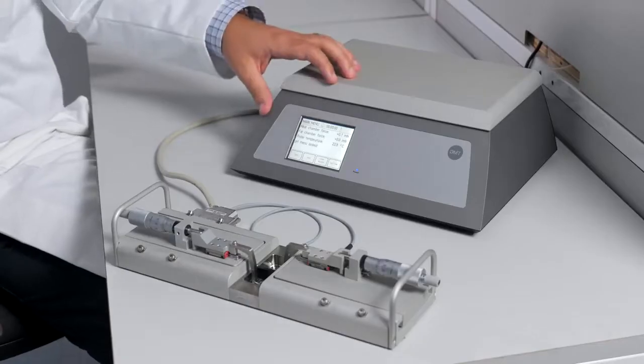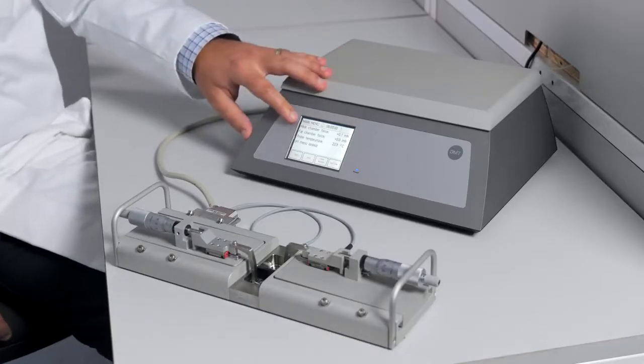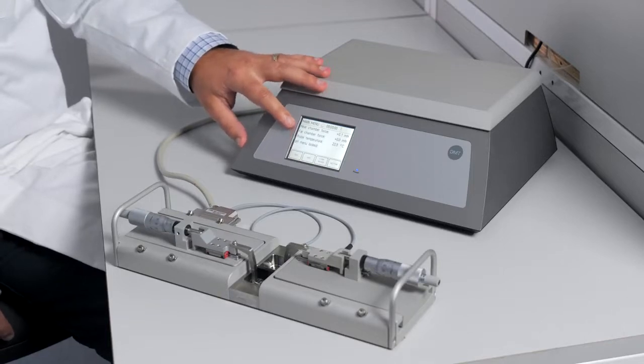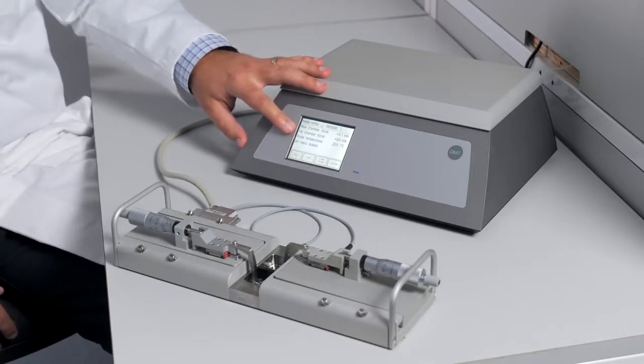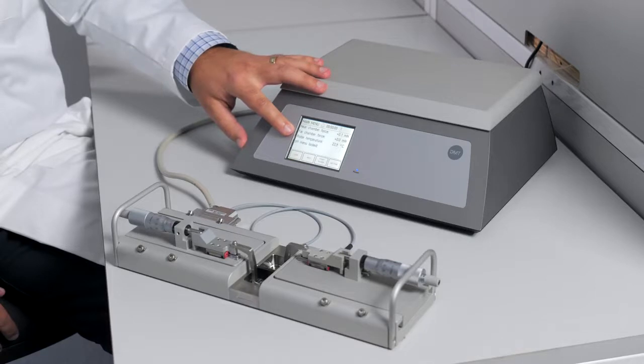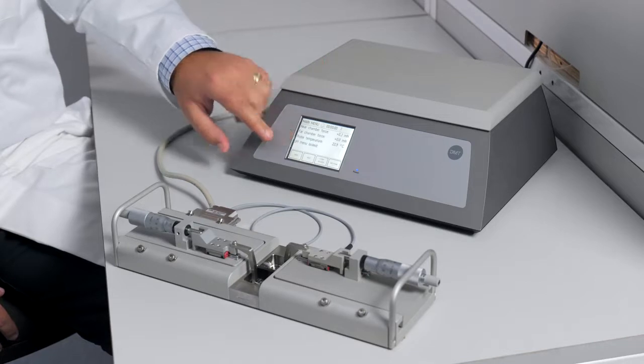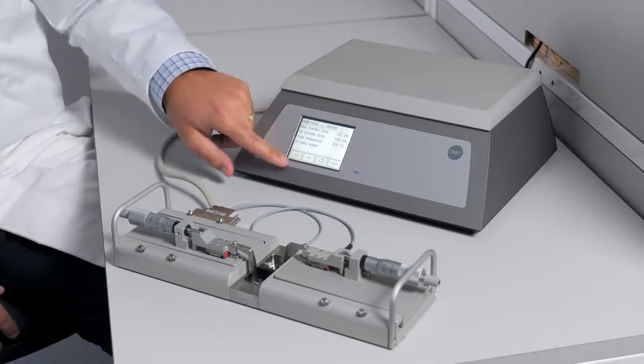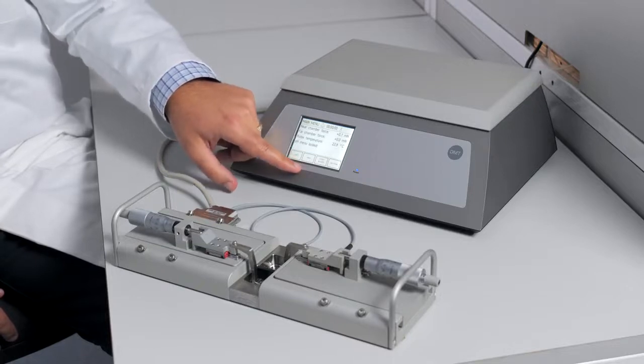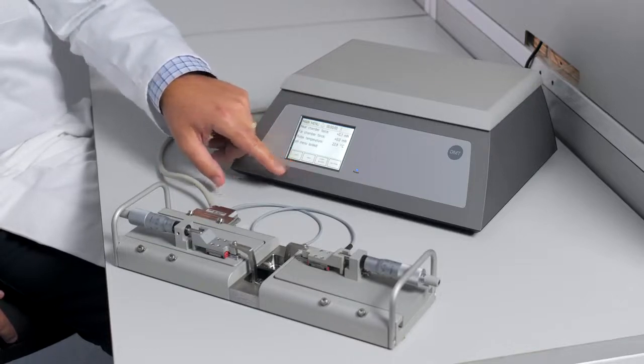We'll begin with the interface, and when looking at the main screen of the interface, you will see the force reading from each chamber, the probe temperature reading, as well as the pH reading if the probe is equipped. You will also use the touchscreen to zero the force reading from your transducers, turn on heat in the chamber, as well as perform the force calibration procedure, as well as other functions that are housed in the interface.